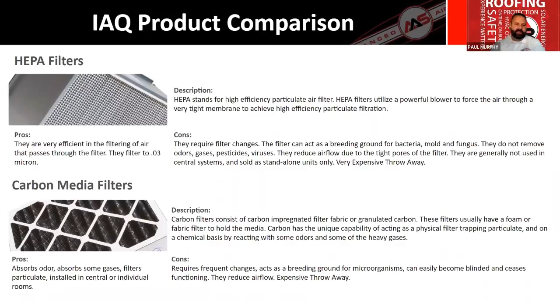The great thing about carbon filters is they're impregnated with carbon. What it means is carbon absorbs odors and absorbs gases, and it's also a filter, so it filters out the particulate. Again, this is an expensive throwaway filter. If you're worried about odors and gases, you go ahead and use this. You can use carbon filters in your standard HVAC system. That's the nice thing about it. You cannot use a HEPA filter in your standard HVAC system. It has to be a separate unit.